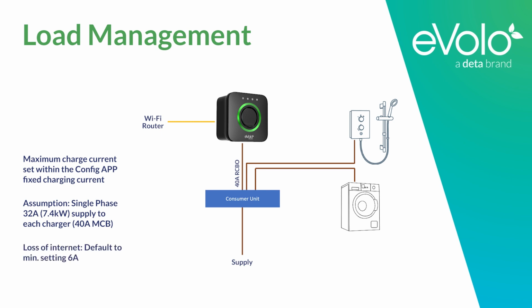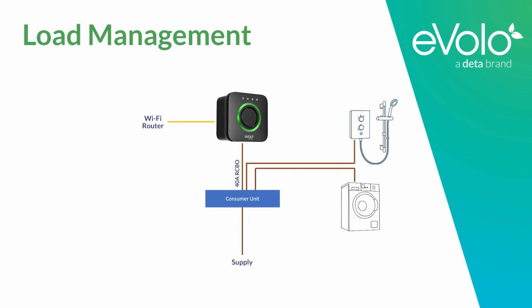With a maximum charge current of 32 amps available, if an EV charge point is being installed at a house with a smaller DNO fuse of 80 amps or 60 amps, your design of the installation may require the maximum charging current to be downrated in order to ensure the safety of the end user. Within the Config app, you can find the setting under User Settable Maximum Current. Once installed, the end user will be able to change the current up to the maximum current set by you in the Config app.